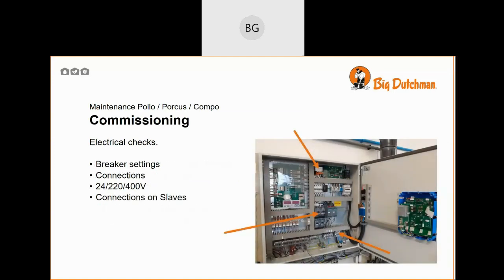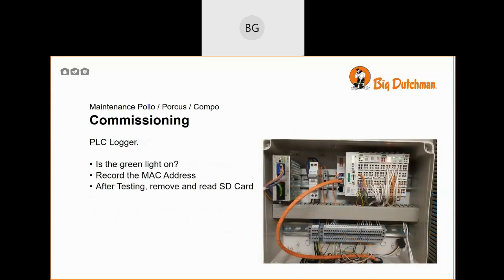Electrical checks. You need to check the electrical breakers are set to the right level, that your 24 volt, 220 volt, 400 volt, 100 volt, or whatever voltages you are using are correct, and that any connections to the slaves are also correct. Is the green light on your PLC logger? On the front side, there is a green light. Record the MAC address, and after testing, remove and read the SD card to ensure that data has been logged. If you're connecting through the internet, remotely connect through the website to ensure that all the information is being logged as required.